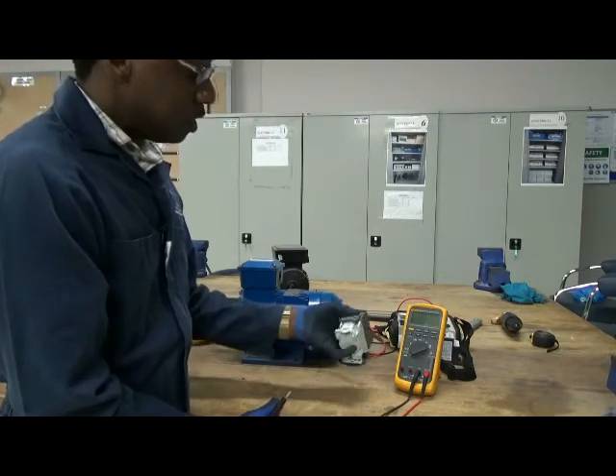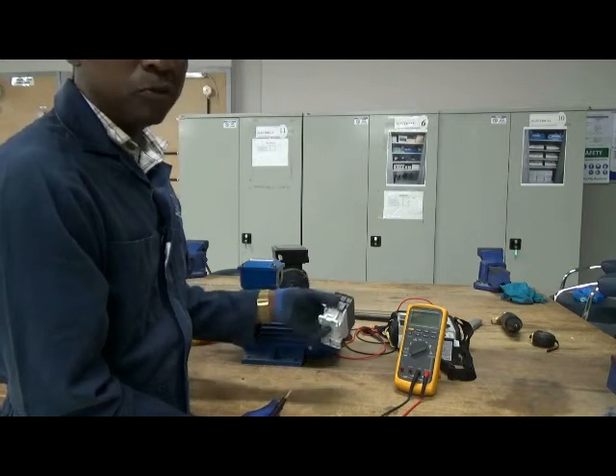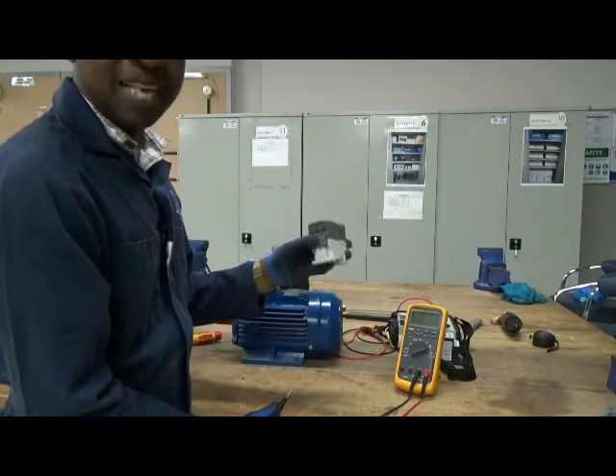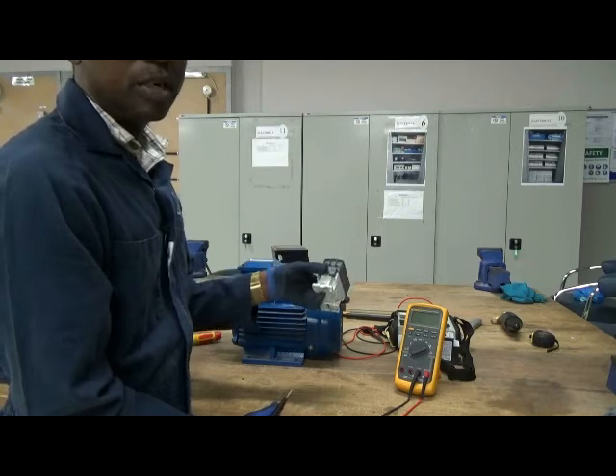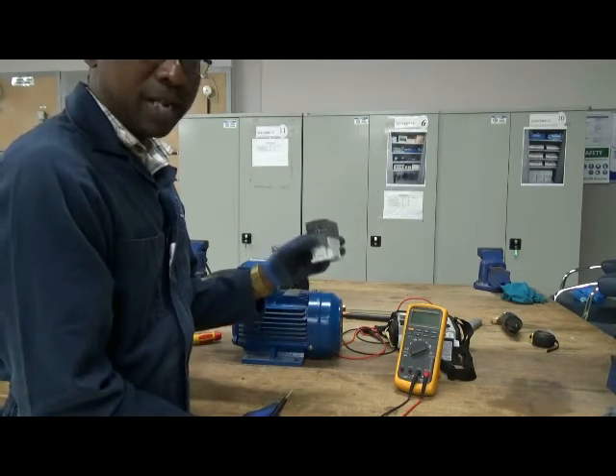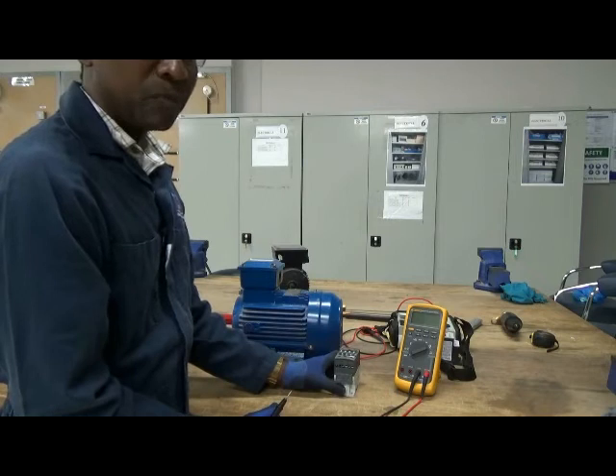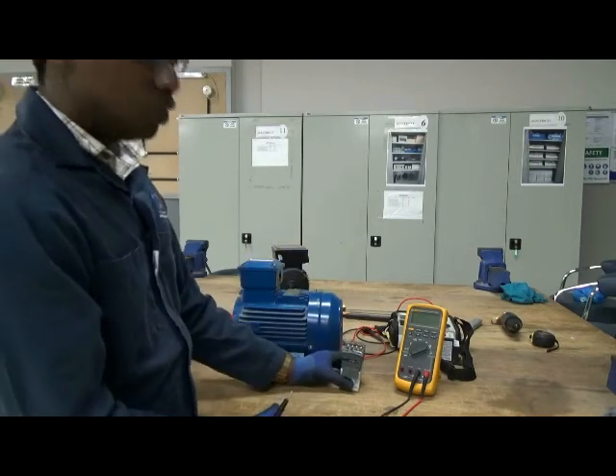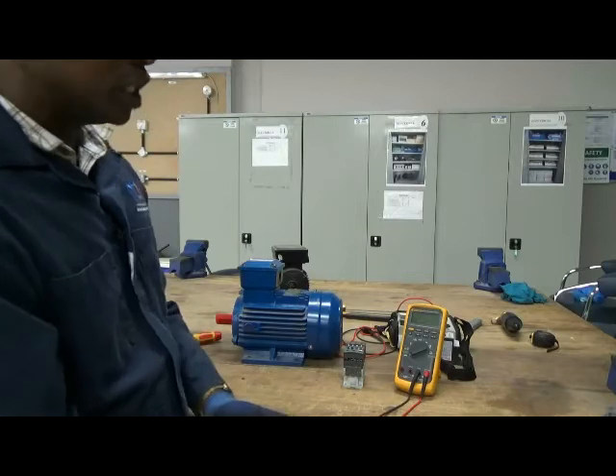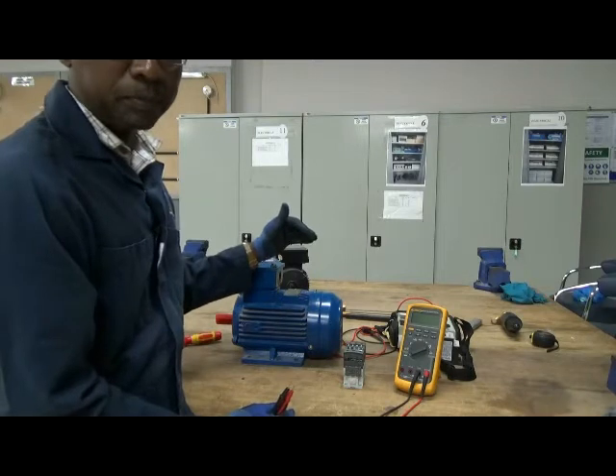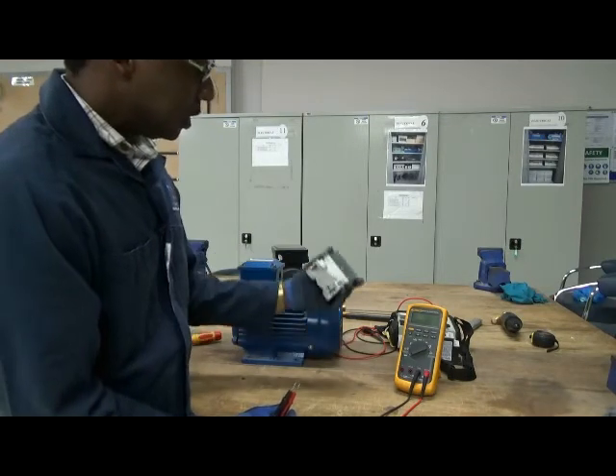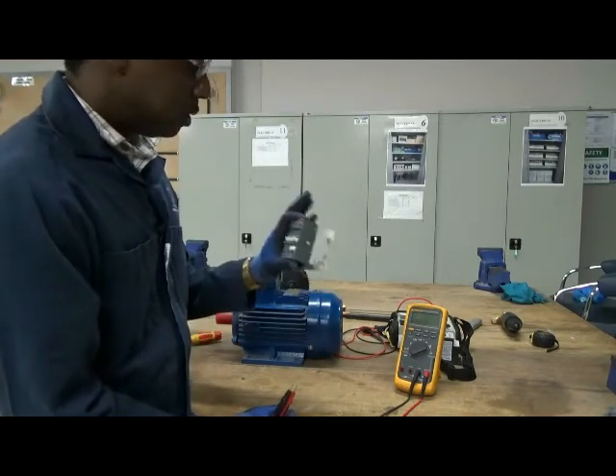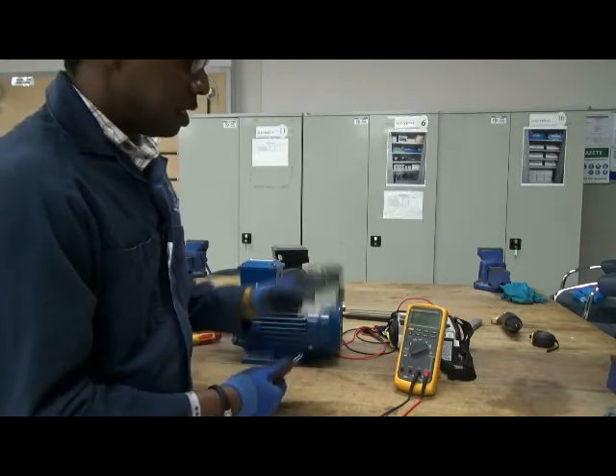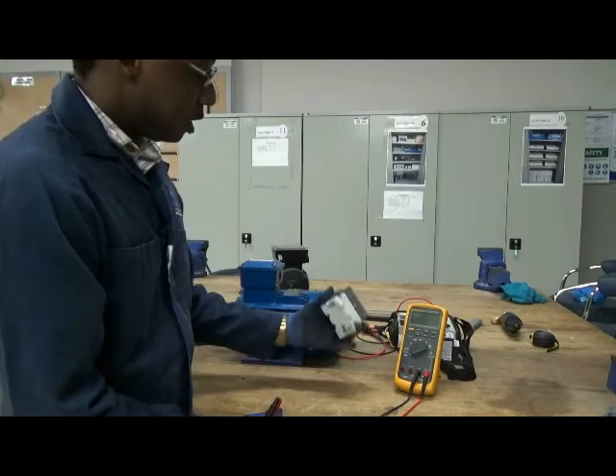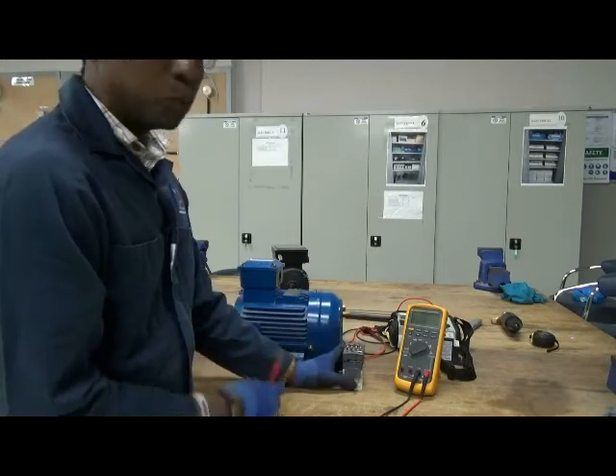So now here we are talking of 415 volts or more, and we want to switch that 415 volts on and off, which means there's a bigger spark when you're switching on and off. But fortunately with this technology, you would not be doing that manually. You are using a lower voltage to switch a very high voltage.